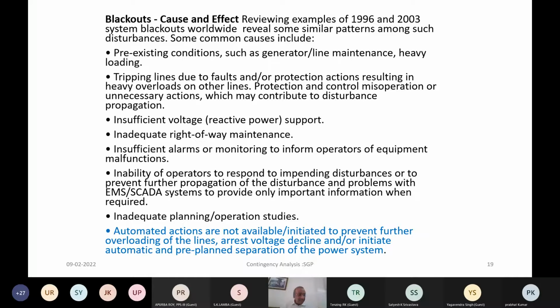I would say geopolitical processes are such that with the agriculture season, giving shutdown to certain areas becomes a socio-political issue, and the decision making on manual opening of the tie lines becomes very critical. And in the process, then automatic action by way of tripping takes place. Of course, so this inability of operators, though they know that line overdrawal is taking place and line loading is increasing, the decision to open the line sometimes becomes a critical factor in prevention of grid collapse.